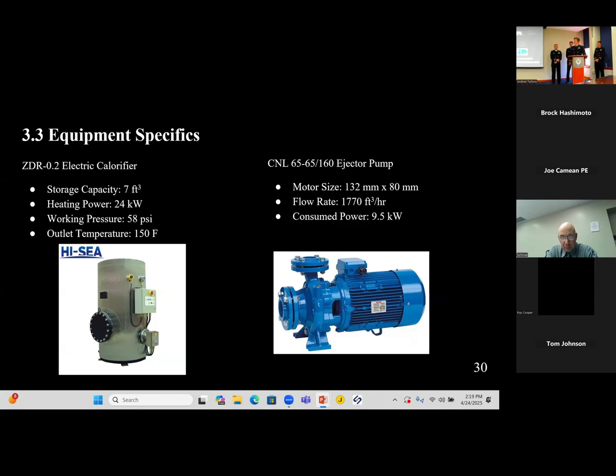The hot water accommodation service line will be equipped with a ZDR 0.2 electric calorifier. This unit has a storage capacity of 7 cubic feet, a heating power of 24 kilowatts, and a working pressure of around 58 psi. The outlet temperature of the freshwater will be 150 degrees Fahrenheit. Finally, along with the distillate pump, the unit also comes with an ejector pump that has a flow rate of around 1,770 cubic feet per hour and a consumed power of 9.5 kilowatts.